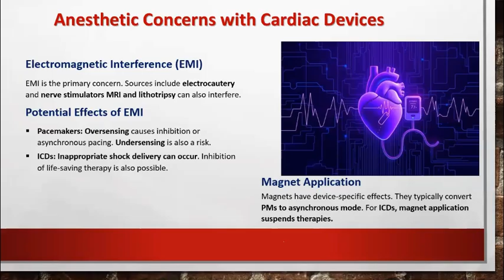Now, only 2 slides for the magnets. Commonly used for the pacemaker in the operating room is usually a medical grade donut magnet. Size is approximately 5 to 8 centimeters in diameter. Magnet strength is more than 90 Gauss at the device. The standard medical grade magnet is 90 Gauss or greater, which is about 180 times stronger than the Earth's magnetic field, which is 0.5 Gauss. So just think about how powerful that magnet is.